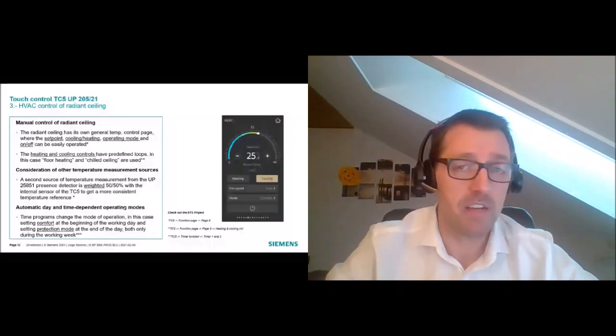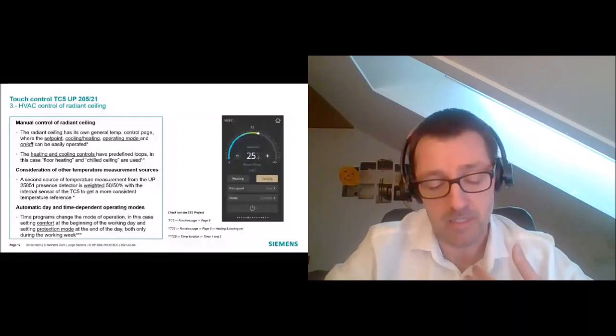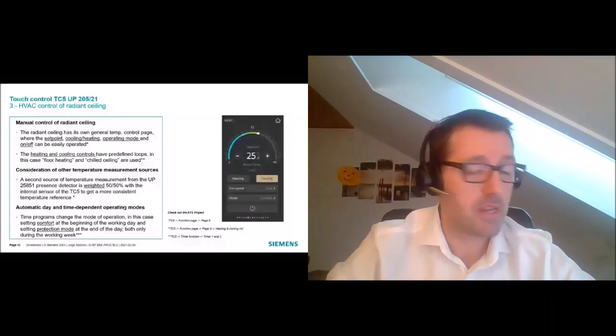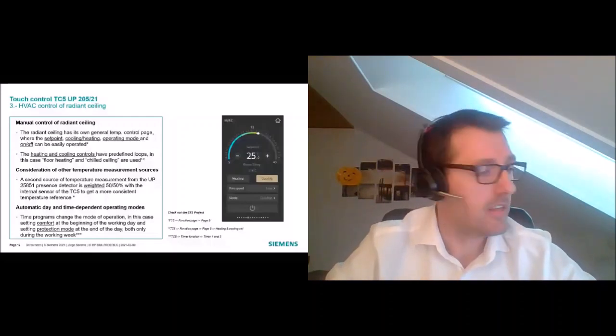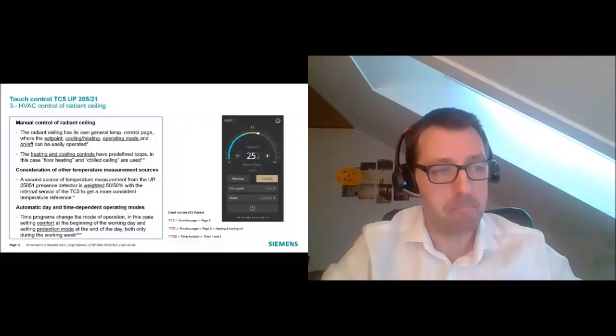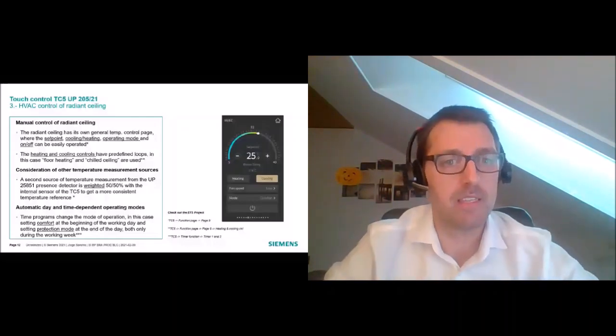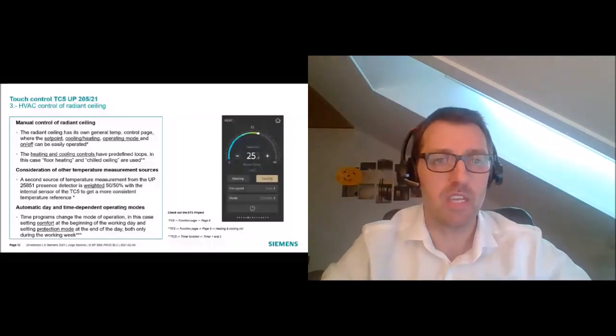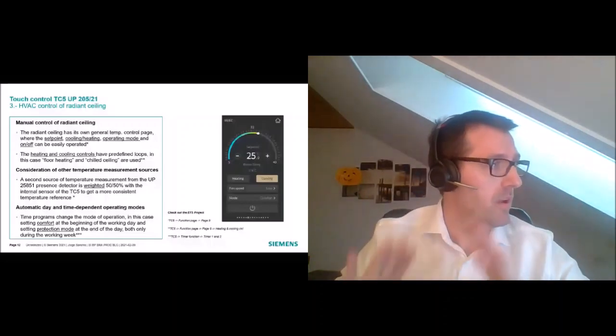For the automatic function, the TC5 has a schedules editor. We just need to create a schedule linked to the thermostat internally — for example, start the working day in Comfort mode and end it in Protection mode. All requirements are met. Check the ETS demo project: with the asterisk markers, you know exactly where to go to see how these settings are commissioned.